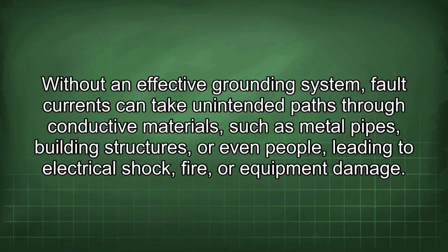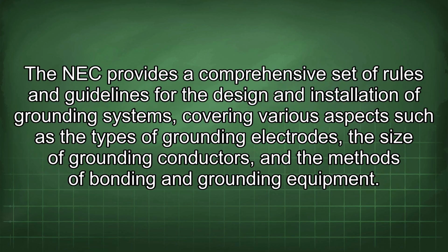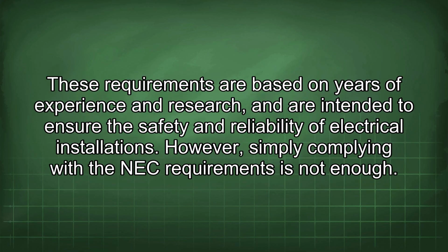Without an effective grounding system, fault currents can take unintended paths through conductive materials such as metal pipes, building structures, or even people, leading to electrical shock, fire, or equipment damage. The NEC provides a comprehensive set of rules and guidelines for the design and installation of grounding systems, covering various aspects such as the types of grounding electrodes, the size of grounding conductors, and the methods of bonding and grounding equipment. These requirements are based on years of experience and research, and are intended to ensure the safety and reliability of electrical installations. However, simply complying with the NEC requirements is not enough.